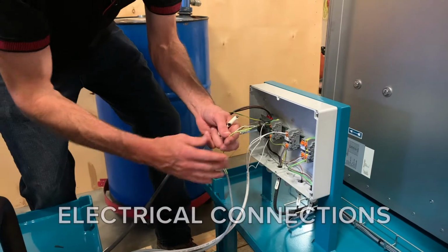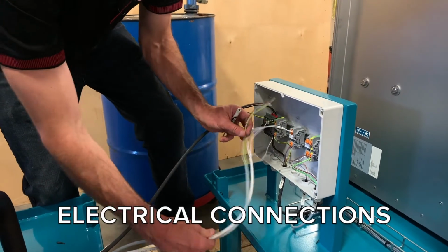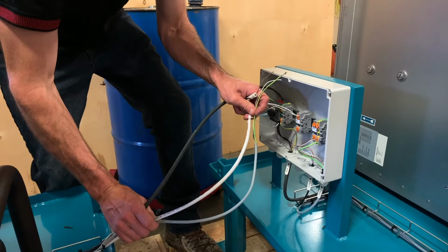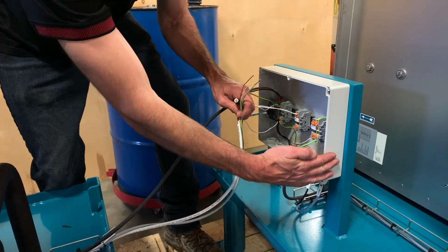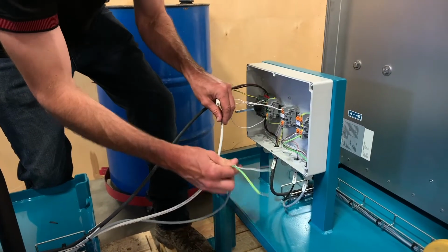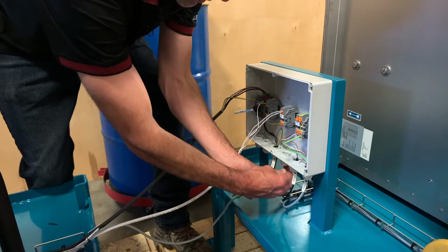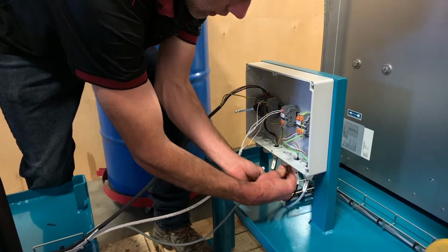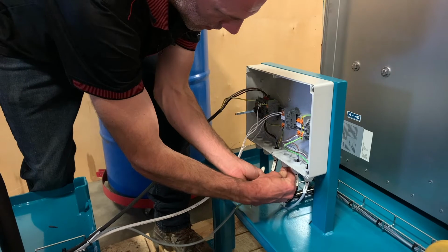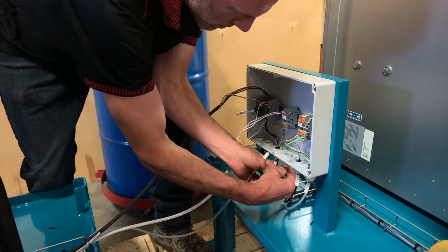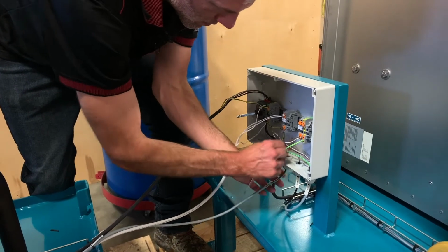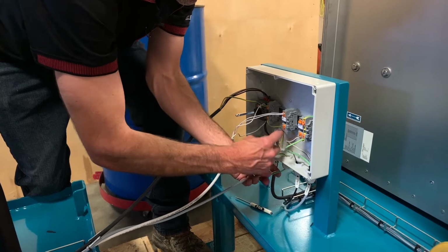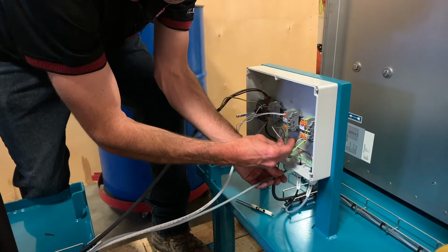The two units need to be connected electrically, and you'll see there's pigtails coming out of the main skid and a junction box on the secondary skid. In order to connect them, you'll run it up through the extra strain reliefs at the bottom of the junction box, and then tie them into their corresponding locations.